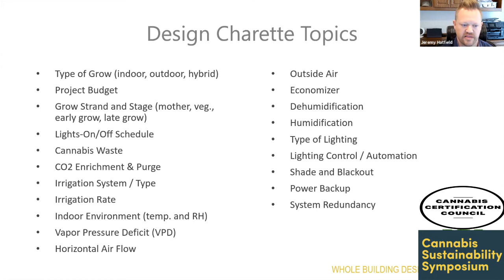So this first example, starting with lighting, I'm going to have a slide comparing high pressure sodium versus LED, and that's going to have an impact on so many things. It affects your lighting control strategy, which affects your first cost. It affects your HVAC system, which can lead to different equipment capacities and mechanical room sizes, which in turn affect energy cost, first cost, and power service size. So this decision needs to be made in conjunction at the beginning of the project with stakeholder buy-in, so we don't start over in the middle of the project if we decide to move to a different type of lighting.